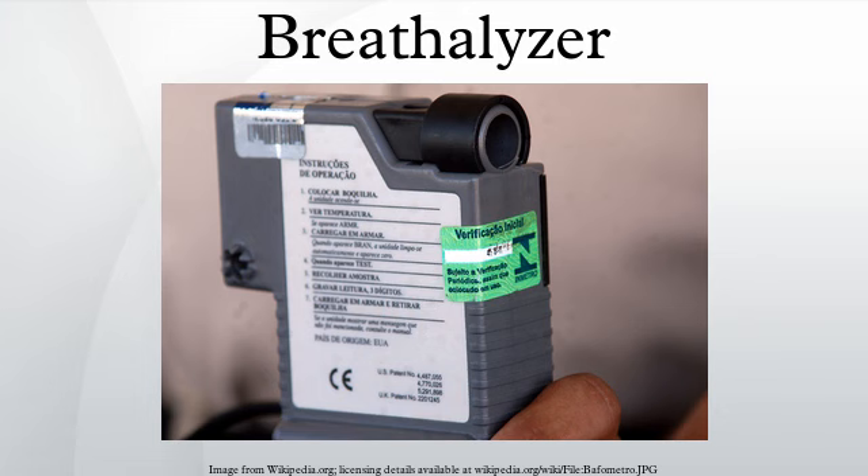Calibration is the process of checking and adjusting the internal settings of a breath analyzer by comparing its test results to a known alcohol standard. Law enforcement breath analyzers are meticulously maintained and recalibrated frequently. There are two methods of calibrating a precision fuel cell breath analyzer: the wet bath and the dry gas method, each requiring specialized equipment and factory-trained technicians. Some semiconductor models are designed to allow the sensor module to be replaced without sending the unit to a calibration lab.